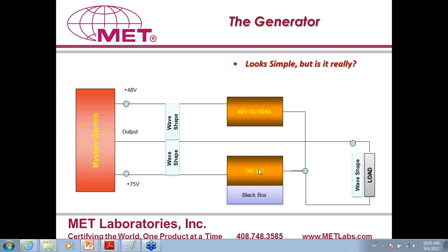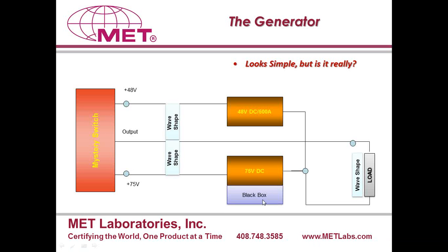The other bigger challenge is the amount of energy. Let's go back for a second to the overvoltage waveform. The overvoltage waveform goes from 50 to 75, meaning 25 volts. We are having a delta of 25 volts within less than 2 microseconds. So that would require a tremendous amount of energy. How can we provide that practically infinite amount of energy so that there is no inertia which would lead to slow response, which hinders a designer from going from 50 to 75 volts in less than 2 microseconds? That I have indicated as a black box.